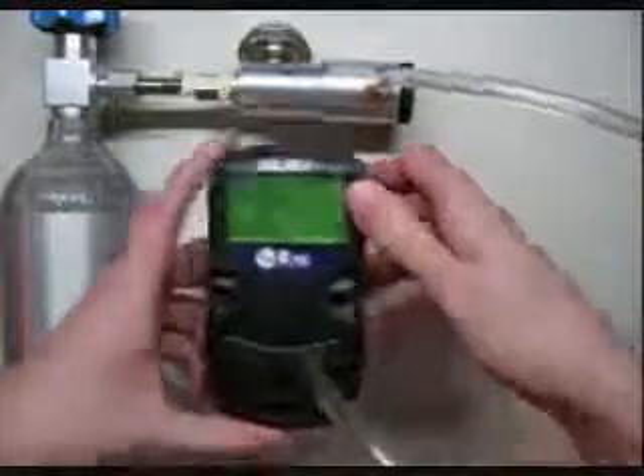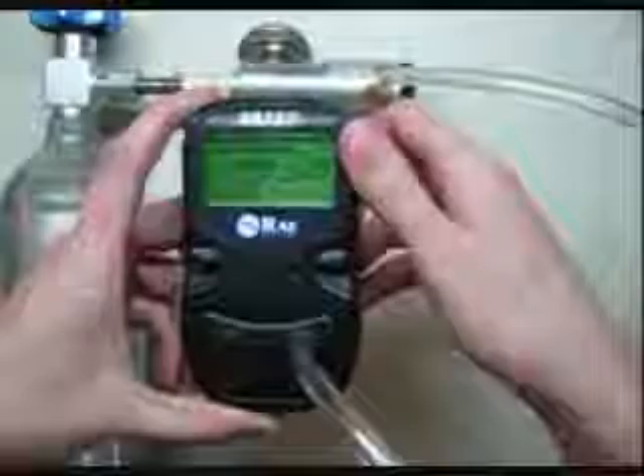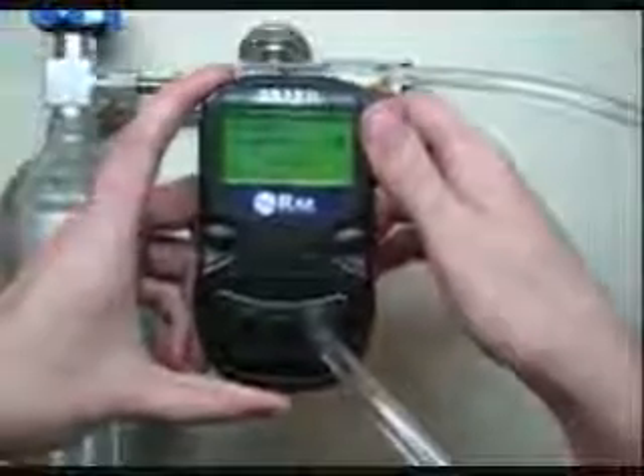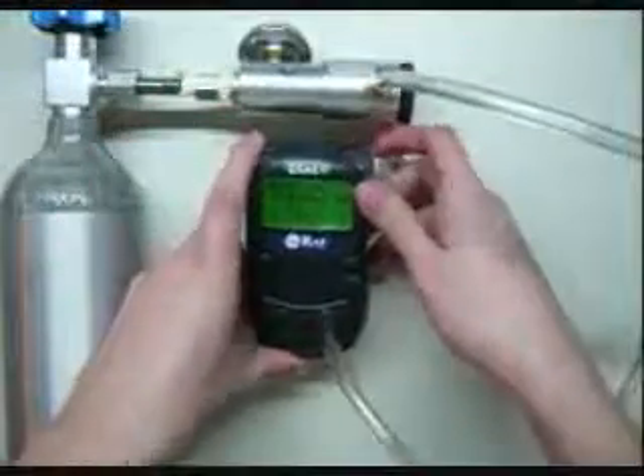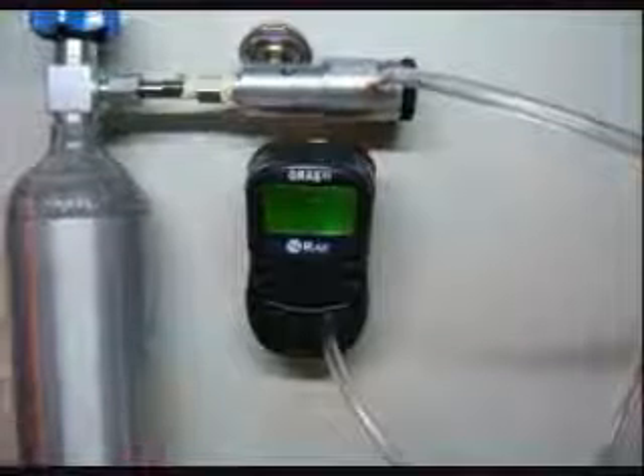Screw this in here. And now we turn on the unit. Turn it to 1 liter per minute. And you can see now that it senses there's gas in there, it'll begin the calibration. It takes 1 minute to calibrate. I'll just let that go.